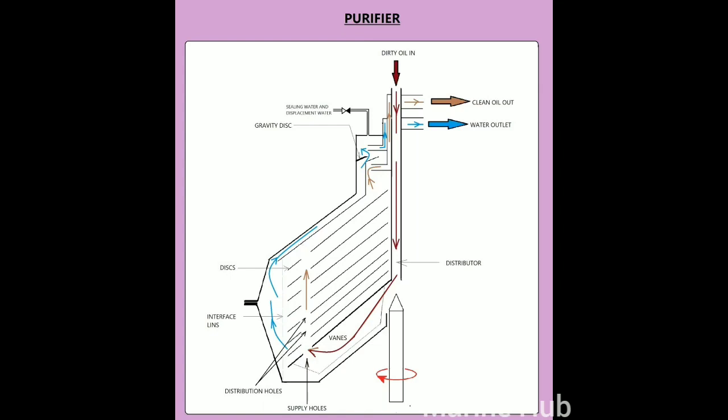The oil passes from the distributor to the bottom of the bowl and from there to the supply holes. From the supply holes, the oil is fed to the spaces between discs through the distribution holes in the discs.